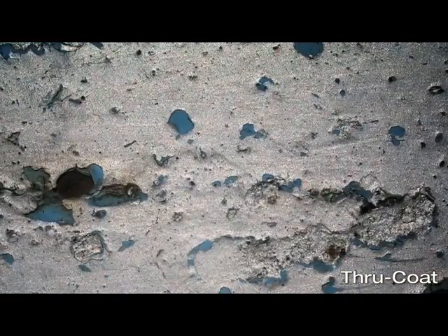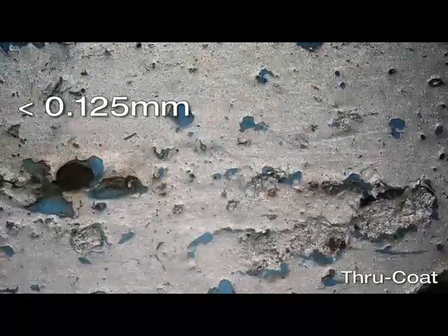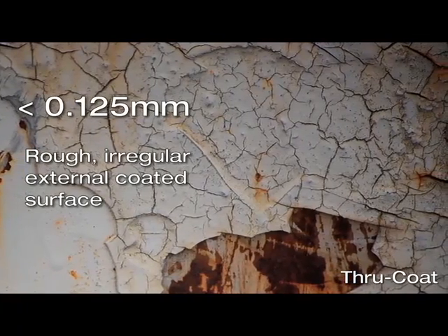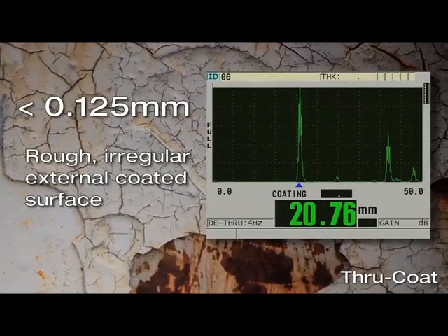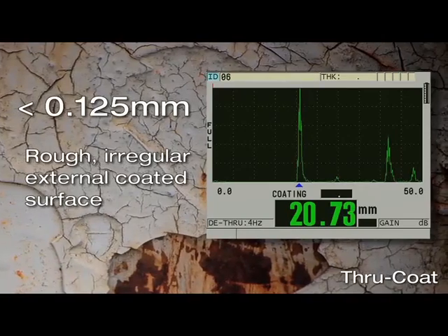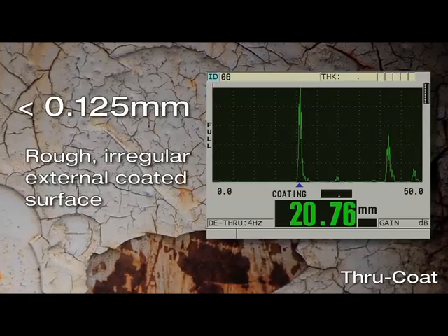The limitations of Thru-Coat are it may not work properly if the thickness of the coating is below 0.125 mm, or if the external coated surface is rough or irregular. It may be difficult for Thru-Coat to resolve the thickness of the coating and the thickness of the steel. When measuring a painted material, if Thru-Coat cannot resolve the coating and steel thickness properly, then the thickness value of the coating will be blank and the thickness of the material will be incorrect.